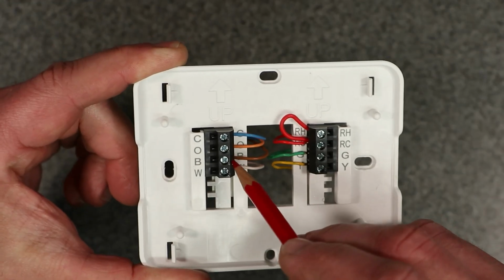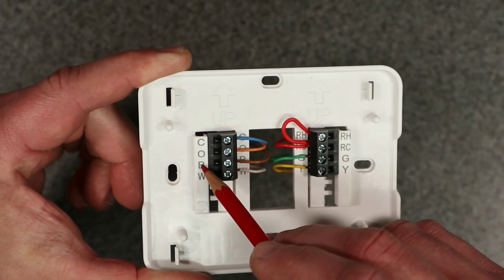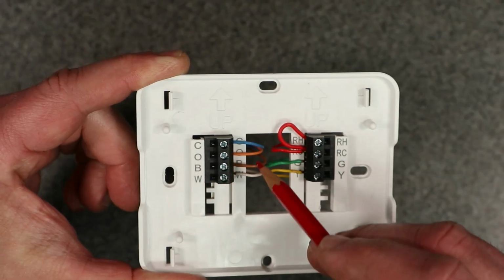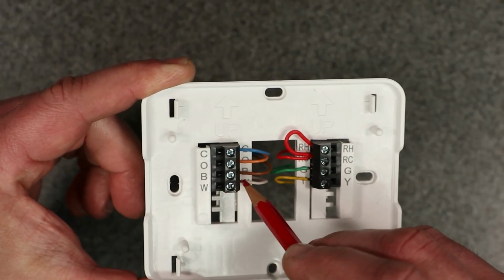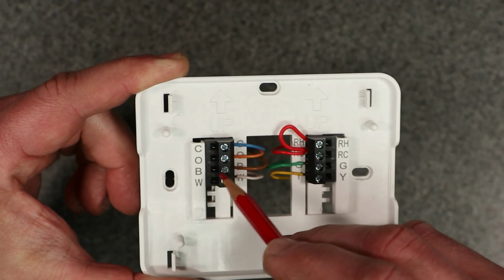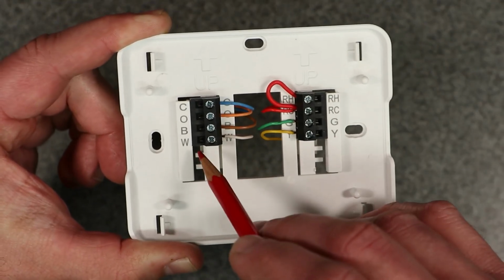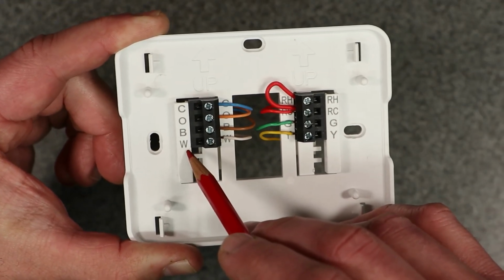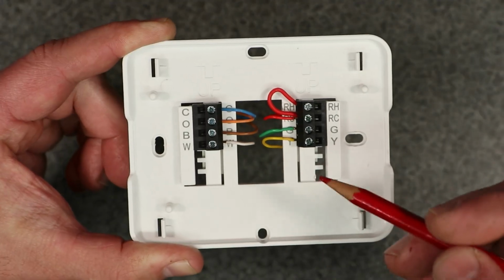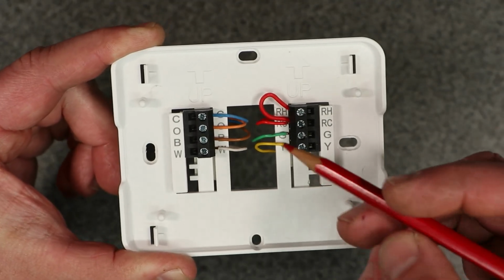The brown wire is for the reversing valve for the heating, okay? So if you had a heat pump used for heating, you would use that. You would have to have the brown wire connected to the B terminal. Also, next we have the W, which is for the white wire. That's for your first stage heating, okay?